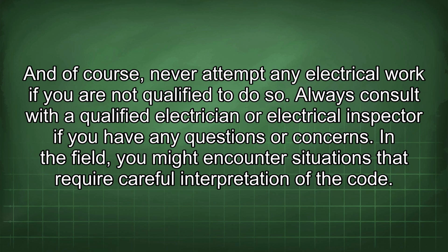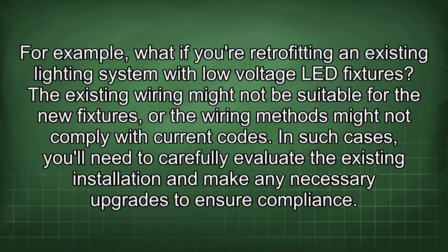In the field, you might encounter situations that require careful interpretation of the code. For example, what if you're retrofitting an existing lighting system with low-voltage LED fixtures? The existing wiring might not be suitable for the new fixtures, or the wiring methods might not comply with current codes. In such cases, you'll need to carefully evaluate the existing installation and make any necessary upgrades to ensure compliance.